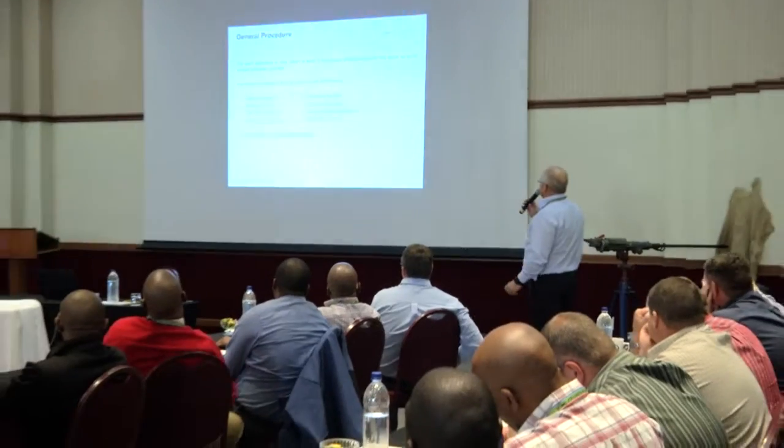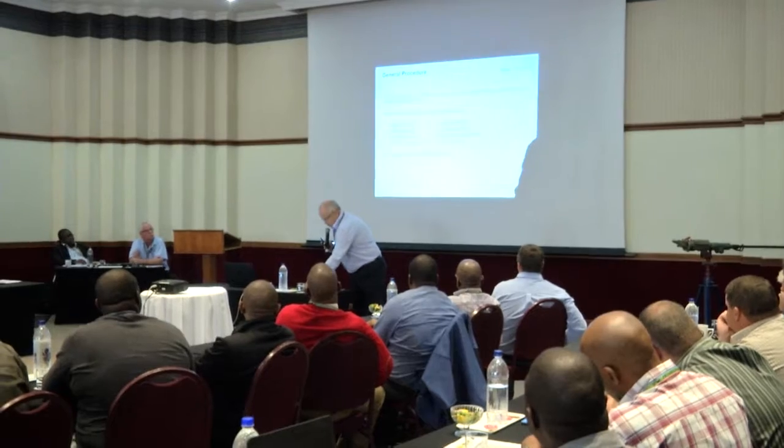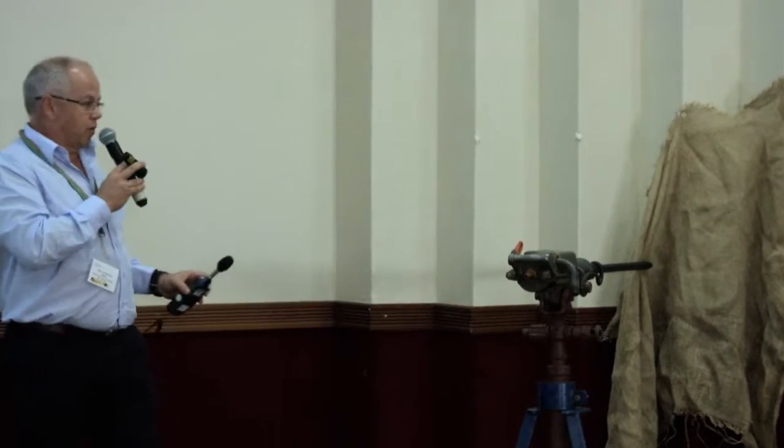Okay, so the general procedure for each workplace or area: select at least 3 microphone positions. The important thing here is that when you measure a rock drill, and you'll see there 1.2 meters from walls or sound reflecting surfaces, the operator is obviously behind the machine. And the operator is almost at arm's length from the instrument, so the operator is most exposed here. But you can take measurements at 1 meter on the left and right of the particular device, depending on what type of equipment it is, and those measurements are then logged accordingly.